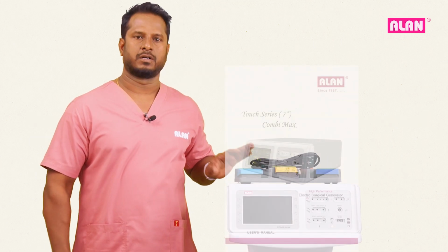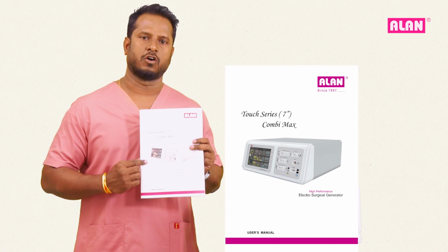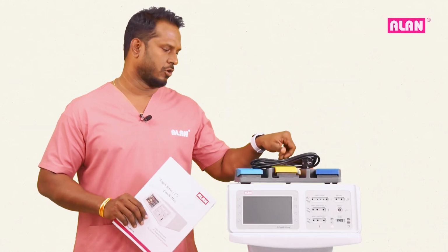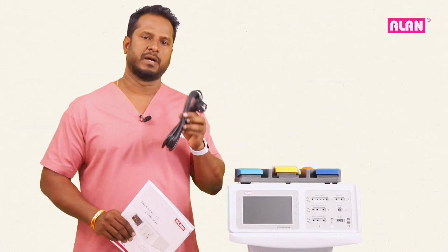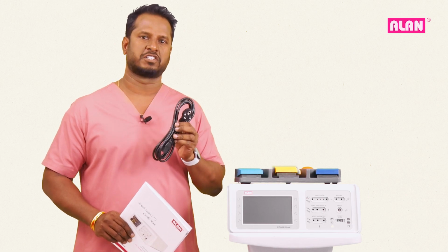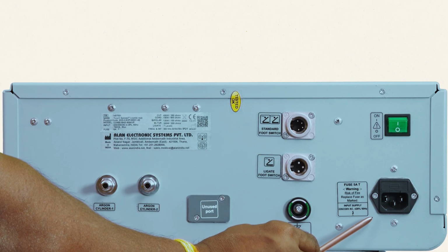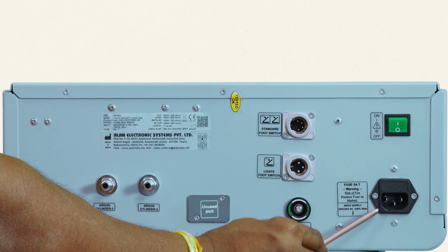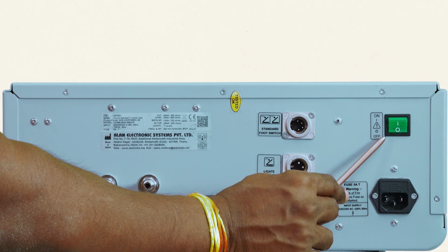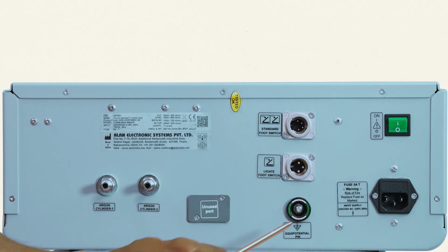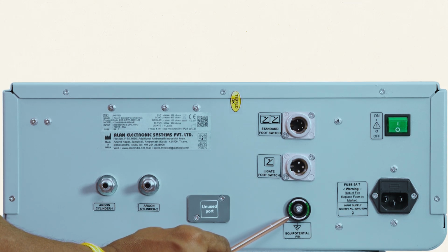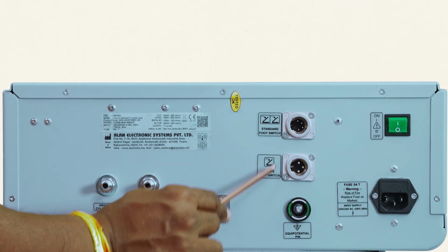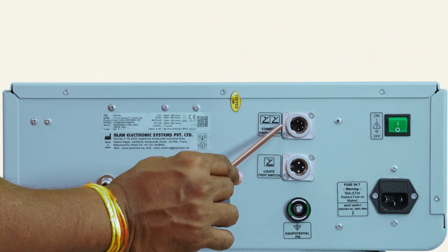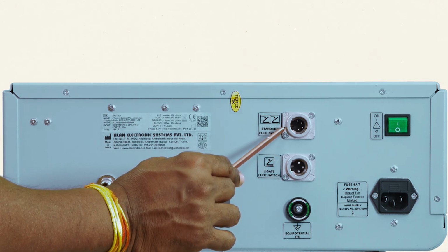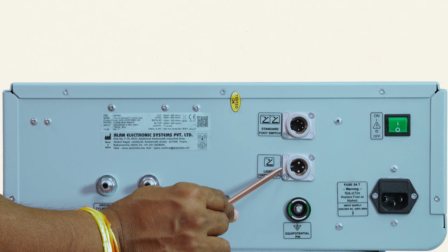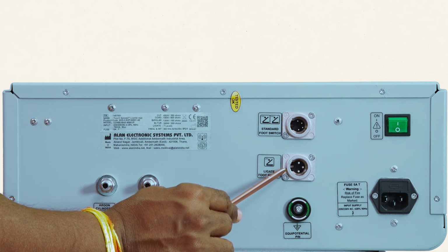Before setting up the unit, always go through the user manual offered by Alan, and always use hospital-grade medical accessories to avoid interrupted services. This is the IEC inlet where you connect the power plug, and using this switch you can turn the machine on or off. This is used for connecting the equipotential cable, and here you have 2 receptacles. Here you can connect a 2 pedal or 3 pedal foot switch, and here you can connect a single pedal foot switch or 1 pedal foot switch.